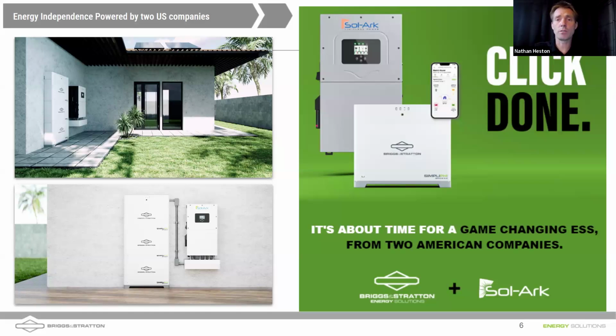As Daniel mentioned, that Sol-Ark inverter—the larger inverter—has come down in cost, with 200 amp pass-through. We now have the ability to pass all of the current from the grid through the inverter to the loads of the home, with that inverter waiting on an outage. The transfer switch is built in—the relays are built into that inverter—so it can automatically manage power coming from the batteries or from the utility to power the whole house.